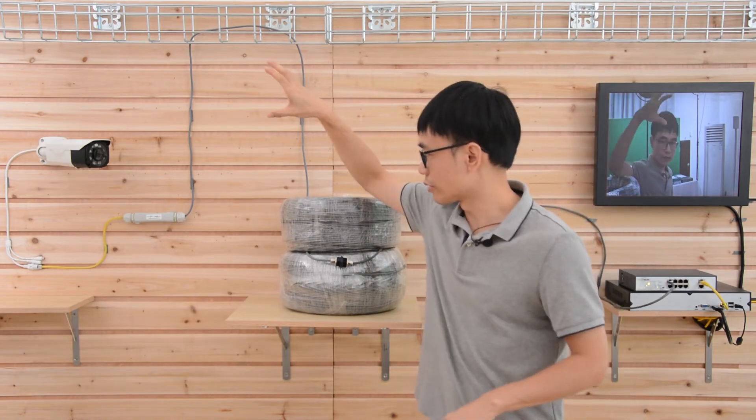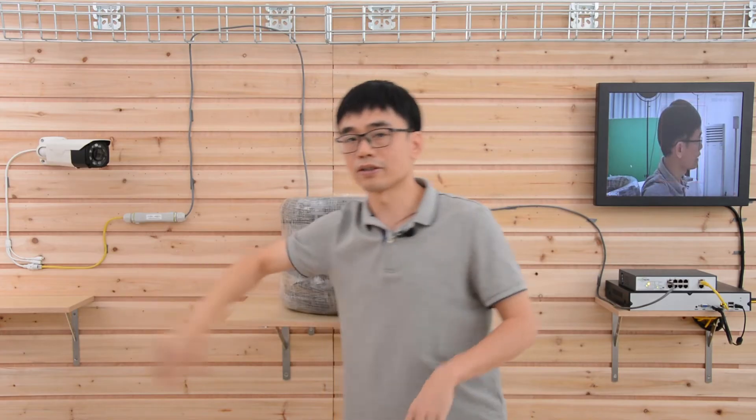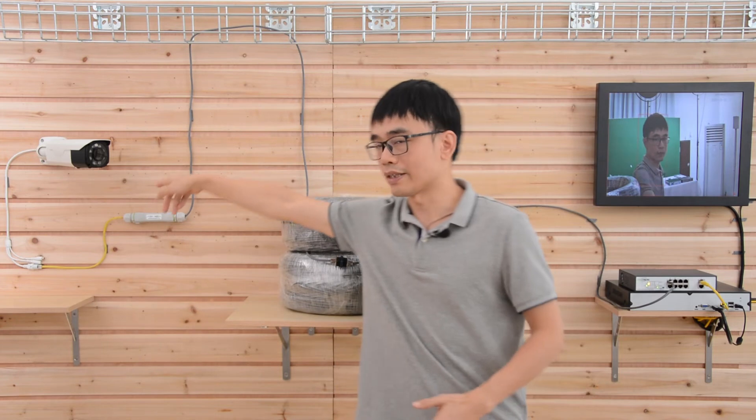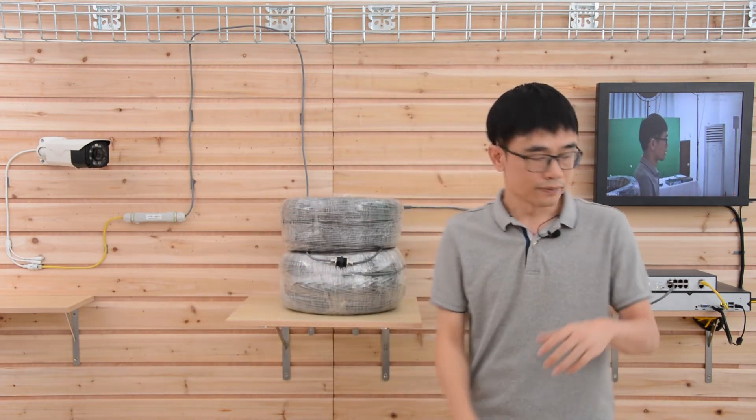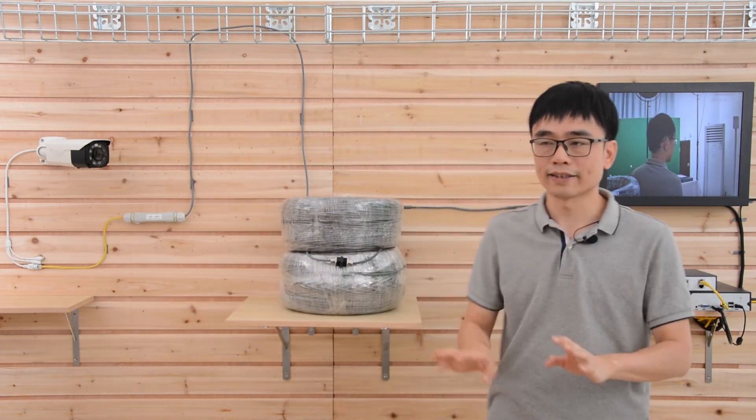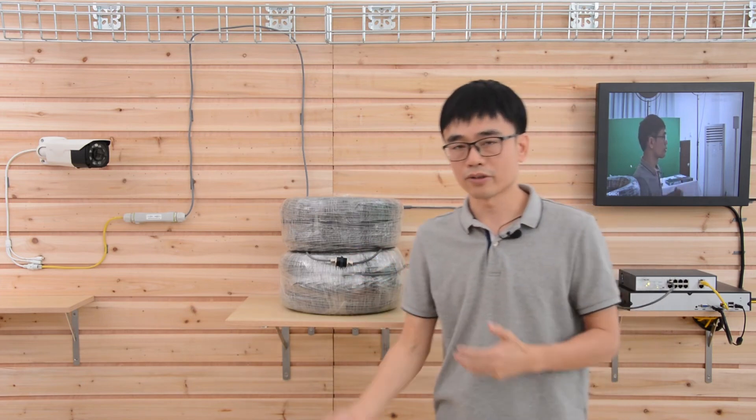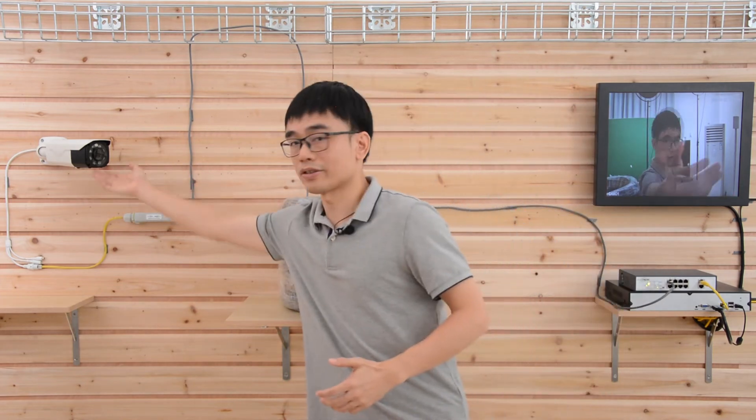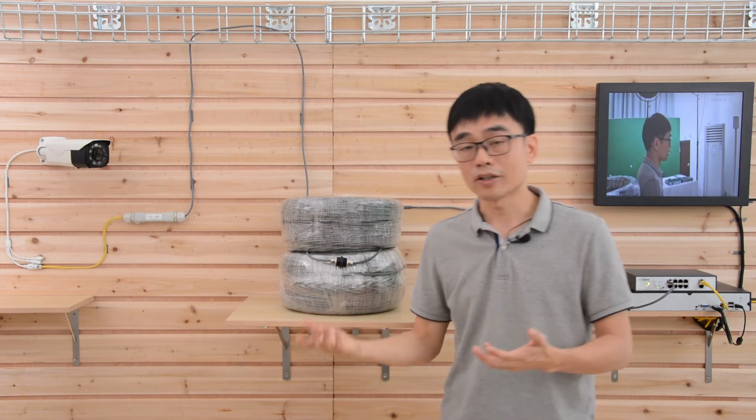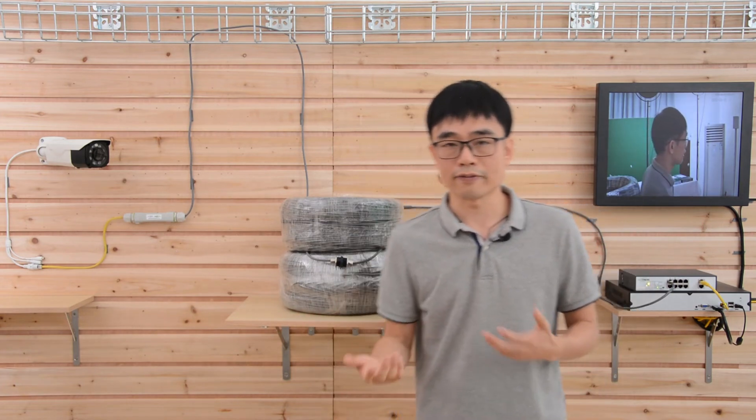But now let's talk about this PoE extender. Why we still need one PoE extender next to the camera. You see, the long run PoE switch can supply long run data up to 2500 feet. But for this one, it's just a regular camera. The data only can reach about 328 feet.